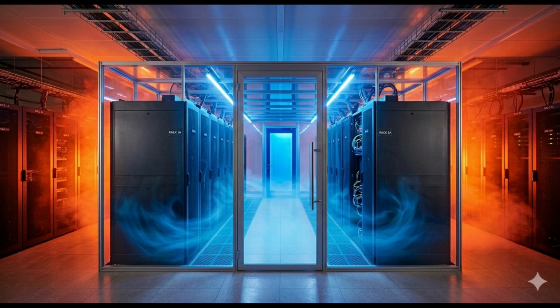Right, V dot is the volume flow rate, cubic meters per hour. It's the actual physical amount of air the fans are pushing. Then CP is the specific heat capacity. Specific heat capacity of air at constant pressure. It's a physical constant. Under standard conditions, it's about 1.006 kilojoules per kilogram Kelvin. It just defines how much energy it takes to heat 1 unit of air by 1 degree.